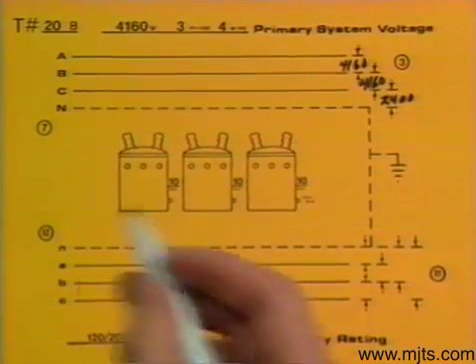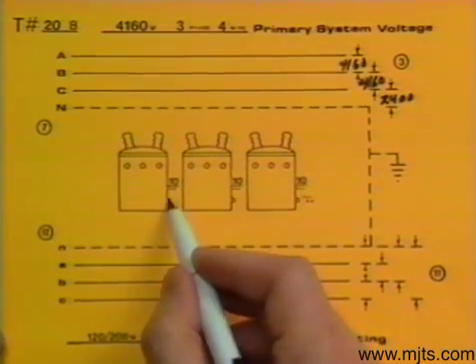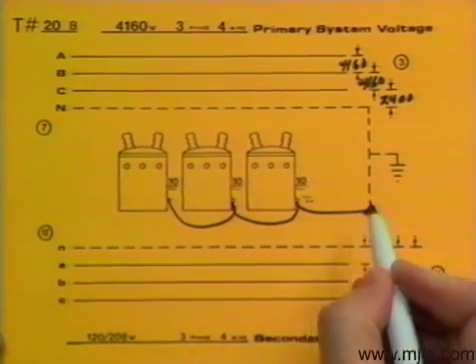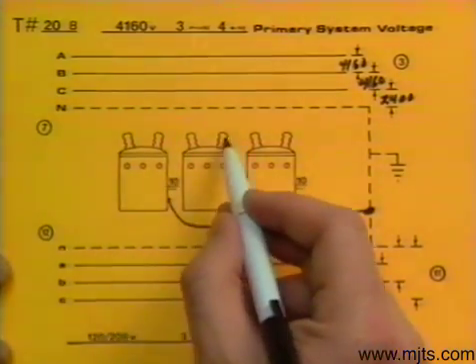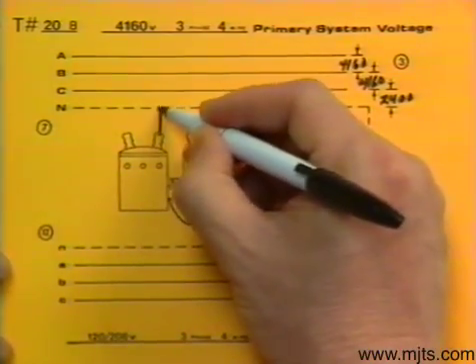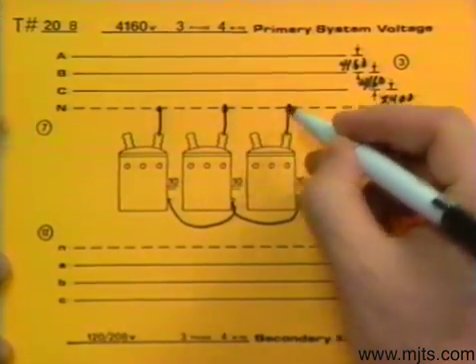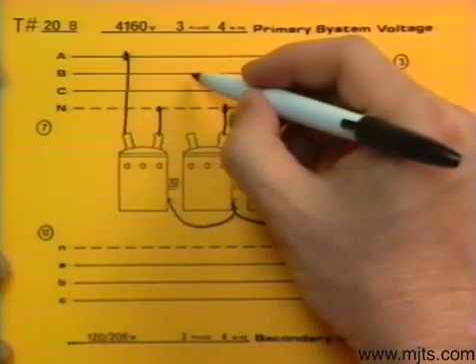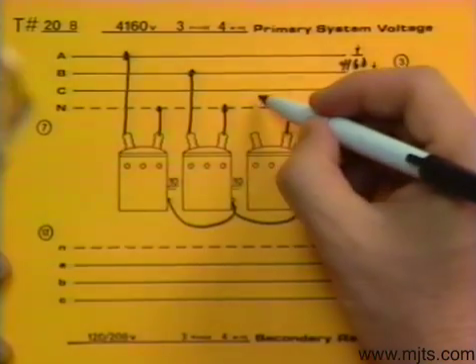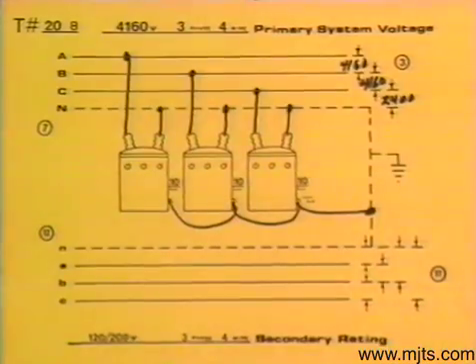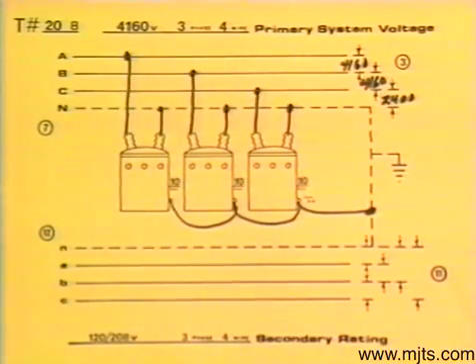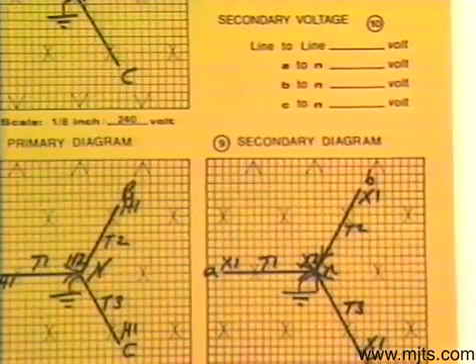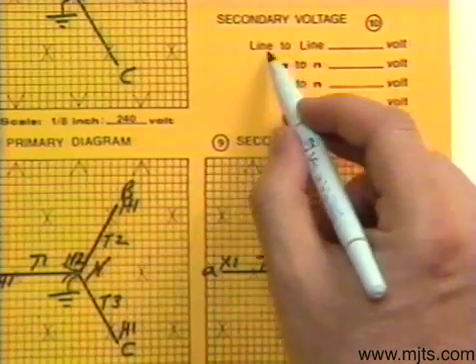We now go back to step seven and make our high-side connection. First, ground out the tubs and make sure protective grounds are on there. All H2 terminals are grounded. Transformer 1 H1 goes to A, transformer 2 goes to B, and transformer 3 H1 goes to C. That completes our high-side connection. We then take step ten and indicate voltages available line to line.